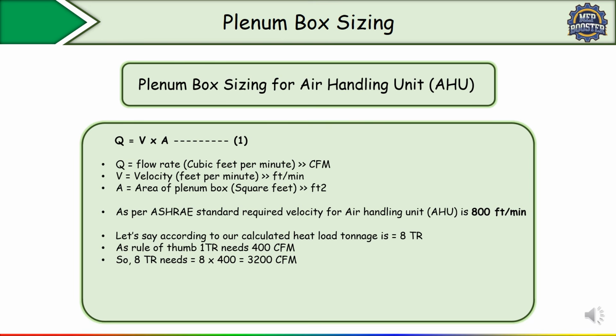Here I have shown you the thumb rule. As per thumb rule we have got 3200 CFM. The exact airflow rate you will get from the cooling load calculation, correct? So here we have the flow rate value in CFM. Now the next thing which we know, as I told you in the start, as per ASHRAE standard, the required velocity for an air handling unit is 800 FPM, correct? So as per equation 1, to calculate the area the formula is Q upon V. Just substitute the values: 3200 is the flow rate, 800 is the velocity. So here you will get the area, 4 square feet.